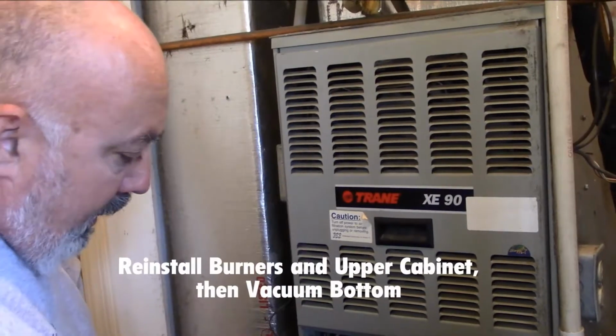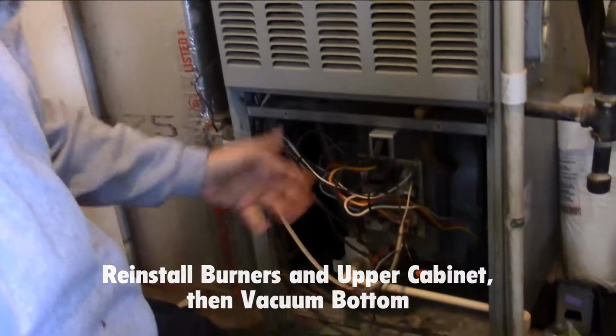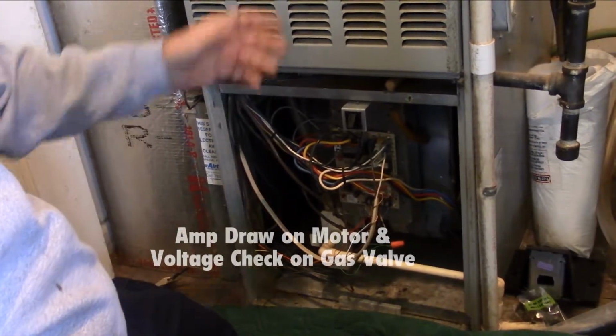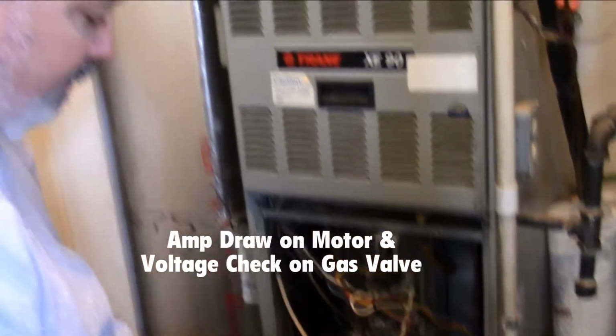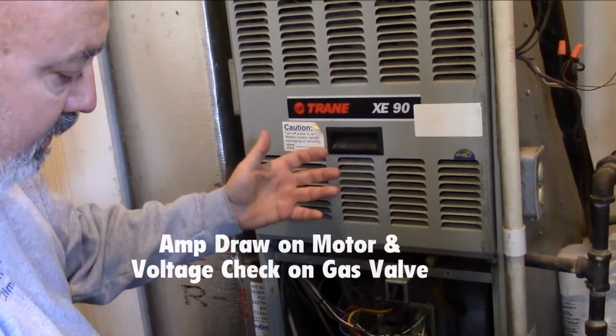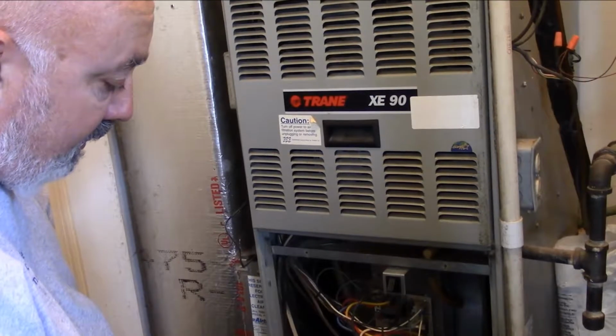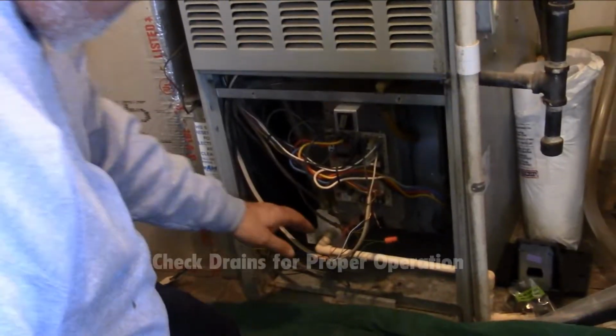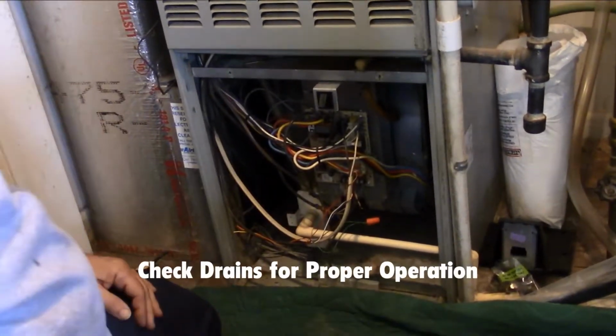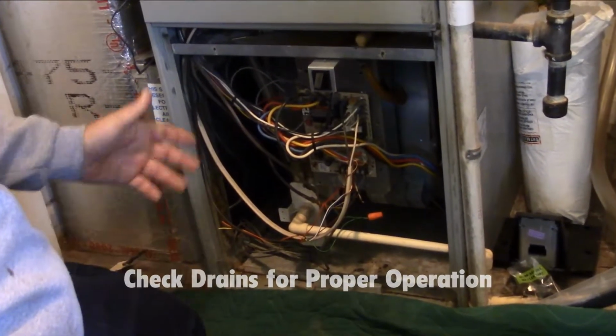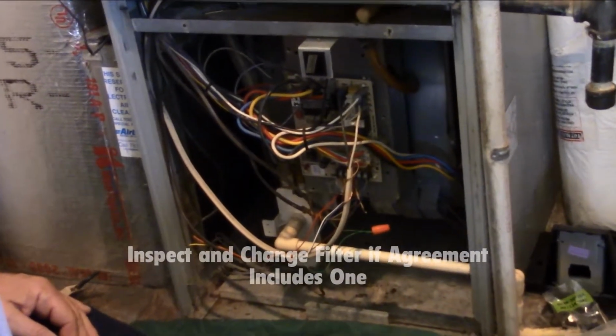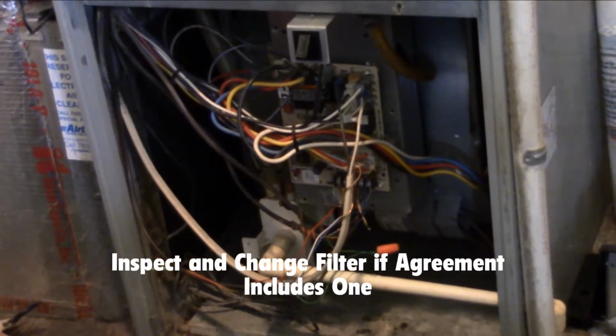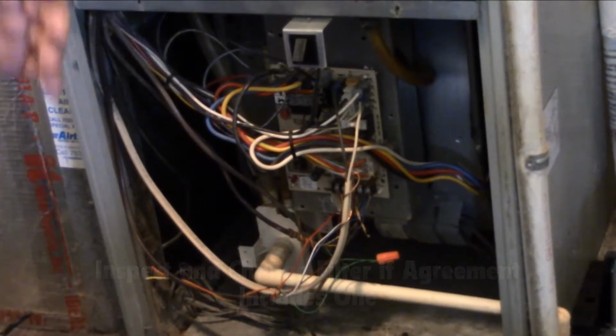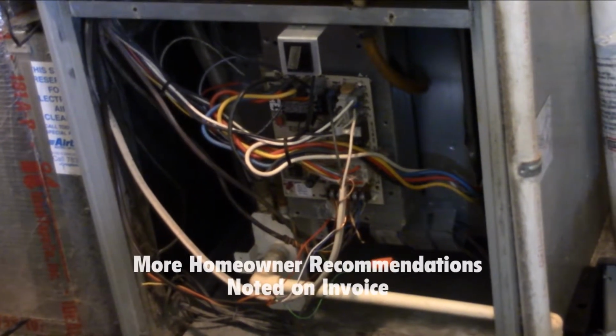All right, now after the burners are put in, we get the cabinet back on up here. We'll then take a vacuum sweeper. We're going to vacuum out everything down here. We're going to fire the furnace up. We're going to do an amp draw on the motor. We're going to do a voltage check on the gas valve, make sure that it's getting plenty of voltage so that you can see when the gas ignites and that the valve opens properly. We'll check and make sure that the drains are cleared properly so that they can drain. We'll also look at your filter for you. Now, unless you pay for it, most maintenances don't provide a filter, but if you do, the filter will be changed at that time. Any deficiencies we find with the equipment, we'll make a note of on the invoice.